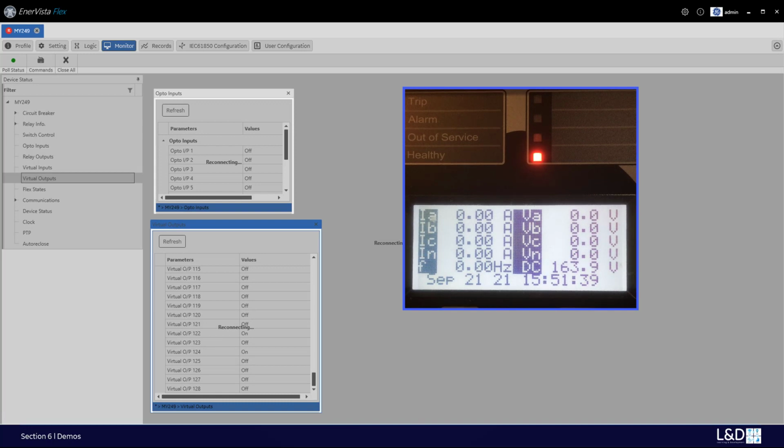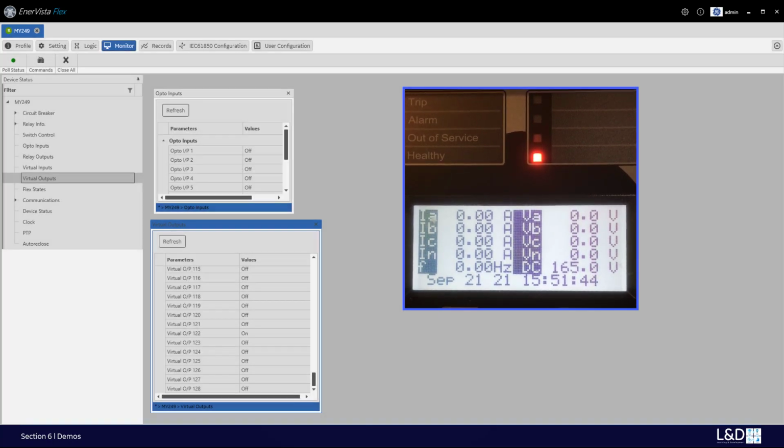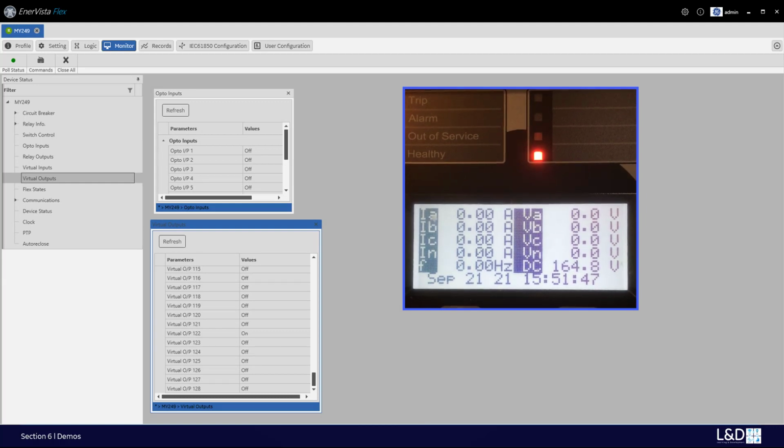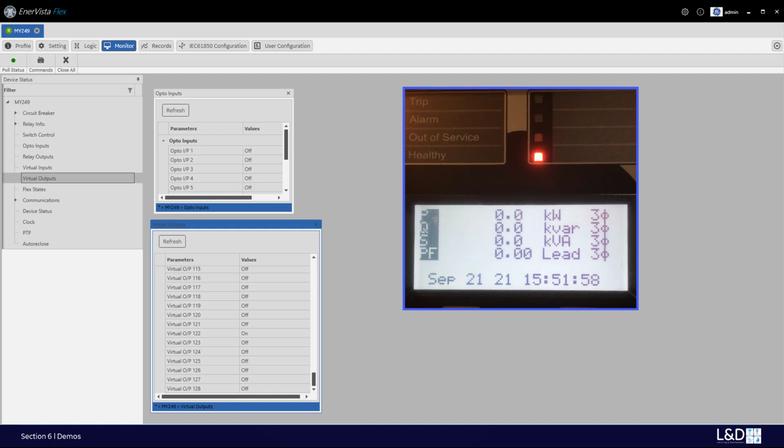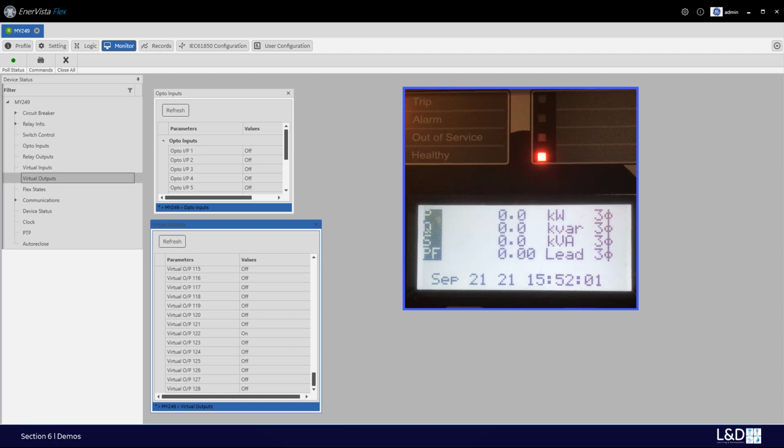Okay, so now the relay finished rebooting. We can see LED 7 is off because that's the volatile latch, and LED 8 is still turned on because that's the non-volatile latch. It means when the power is back after being lost, the latch stays on. And that concludes all the demos for the logic gates.